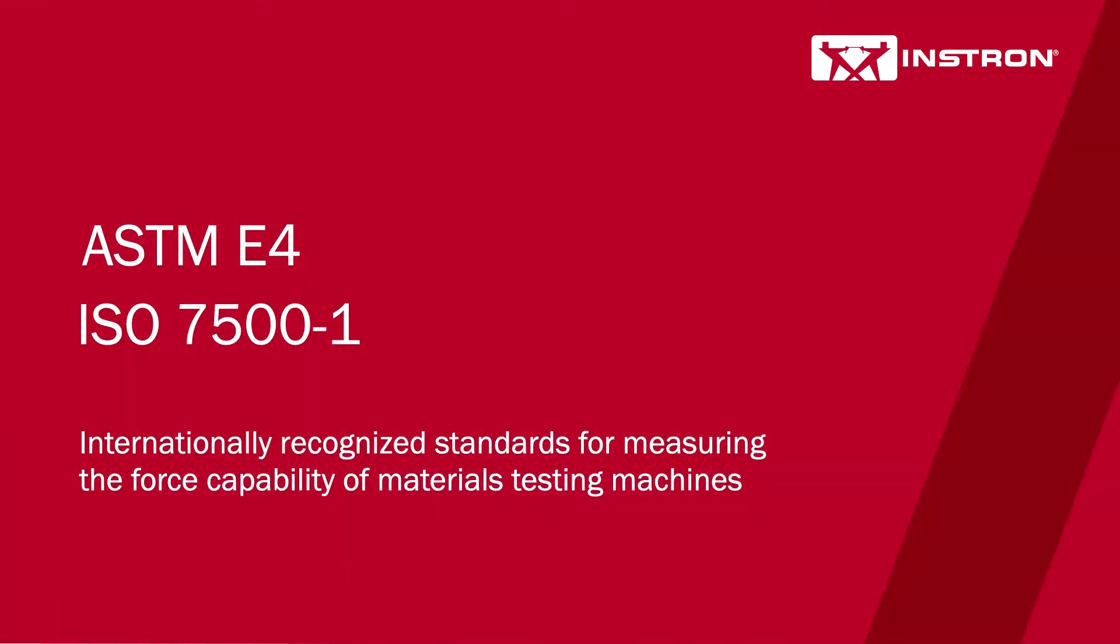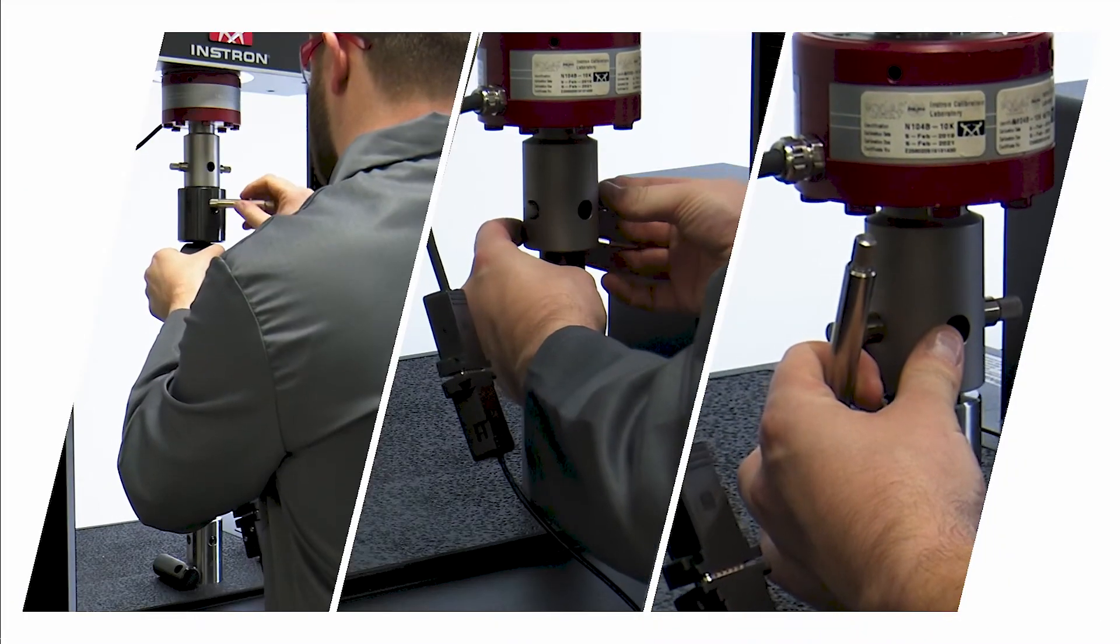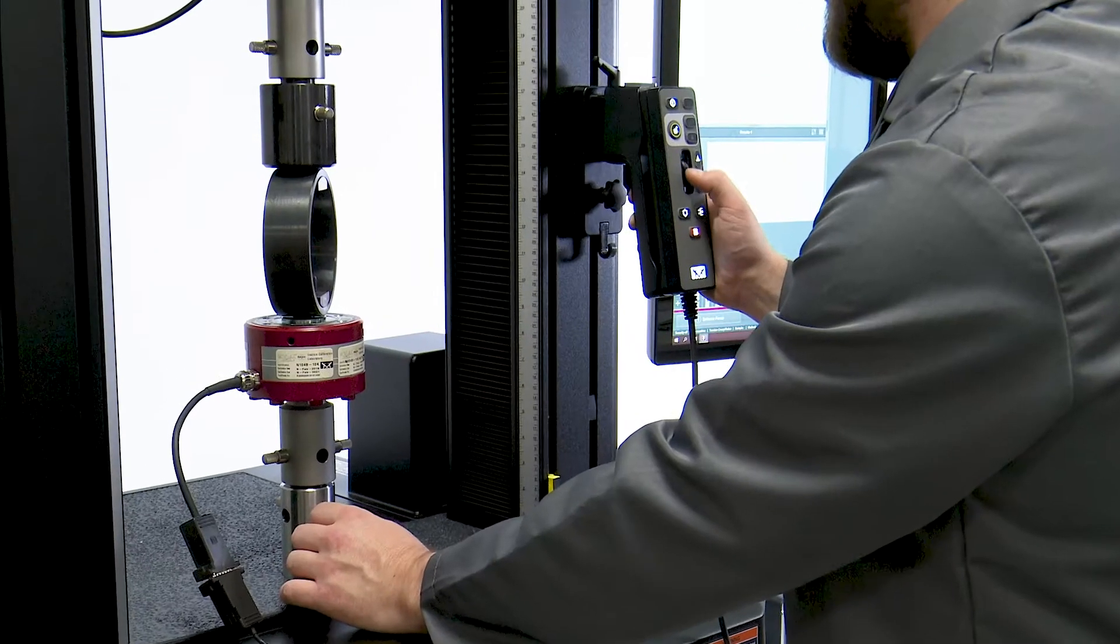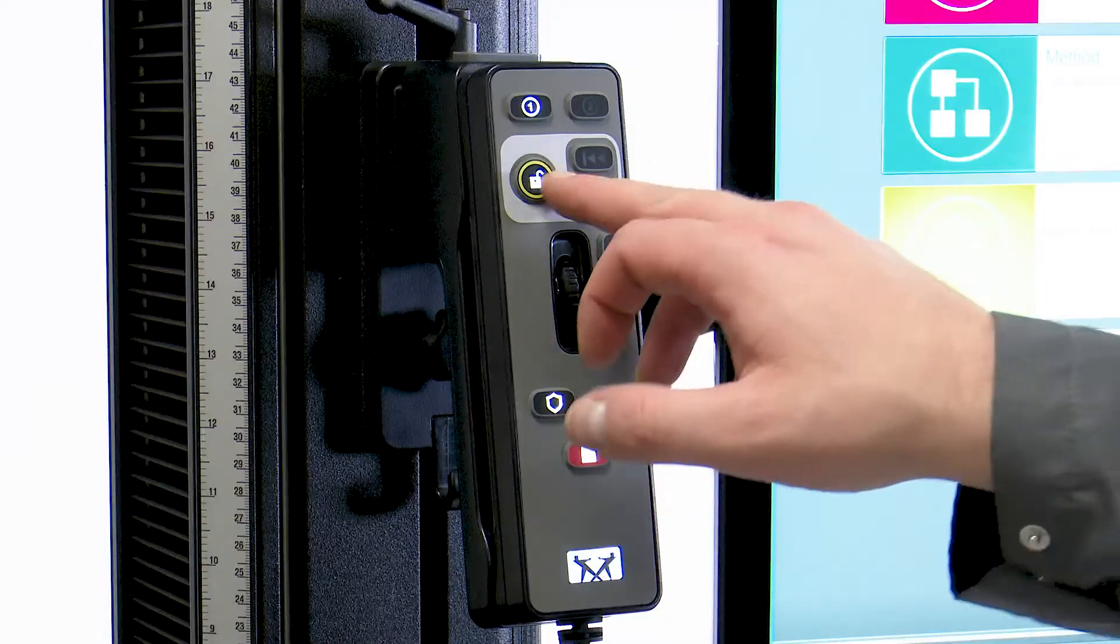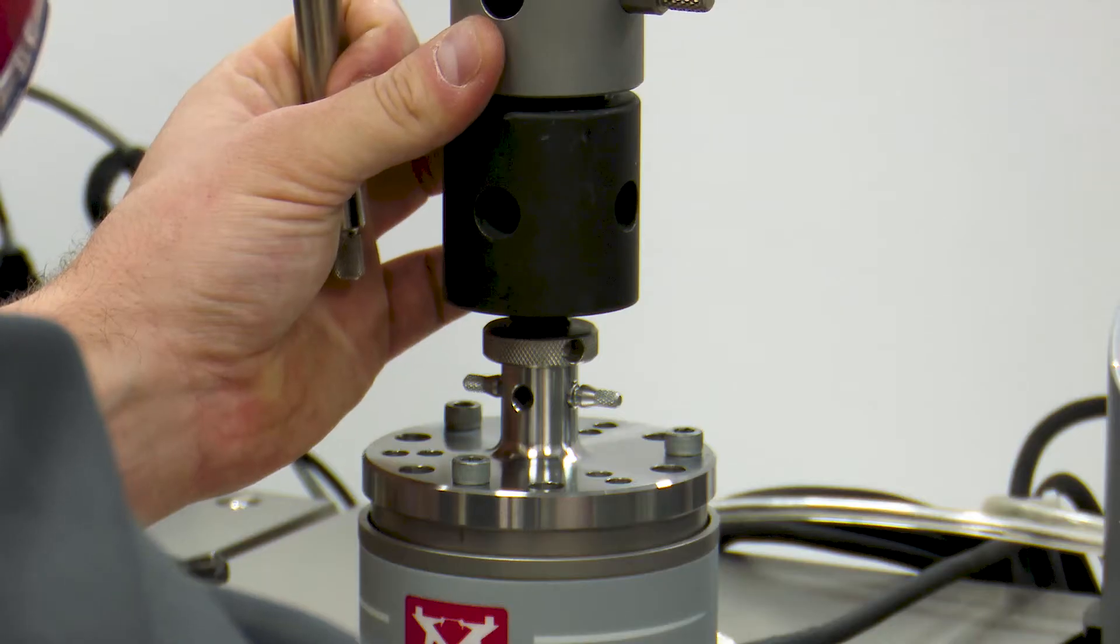Verifying equipment to either ASTM E4 or ISO 7500-1 standards is an important and low-risk way to ensure that your FORCE transducers have been calibrated properly and to reduce the risk of receiving bad data from the instrument.